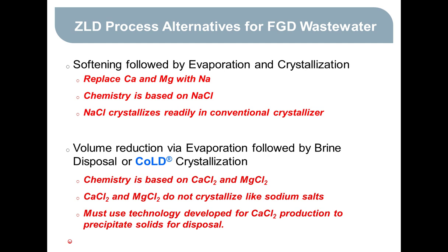Or if we don't want to soften, because softening requires the use of lime and soda ash and it produces a lot of sludge, there's another set of techniques that we can use, which is to use a regular falling film evaporator and then either take the brine and dispose of it somehow from the evaporator, not crystallize it at all, or use what we call a CoLD crystallizer. And that's the new technique I want to talk to you about that has some very interesting economic implications for FGD wastewater. But let's look at these alternatives first.